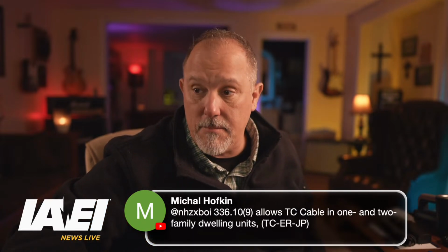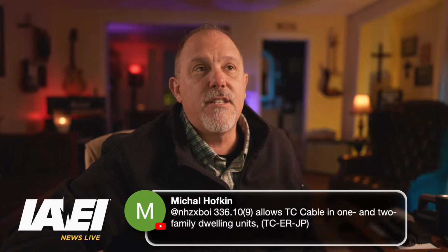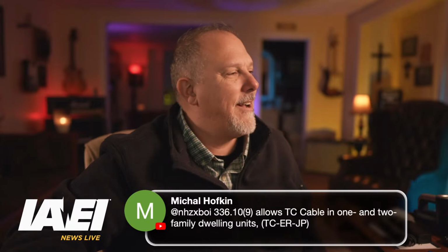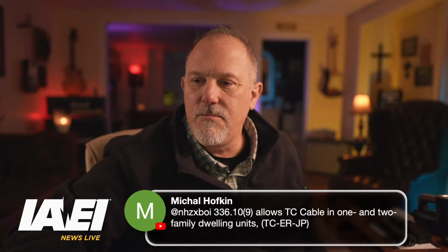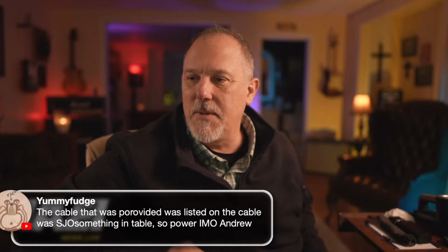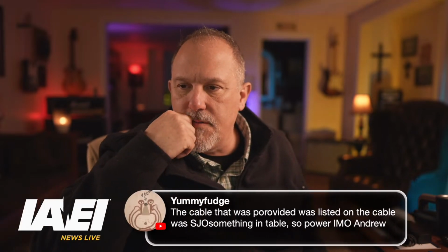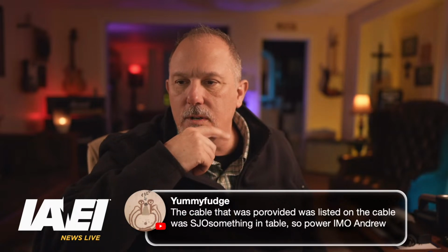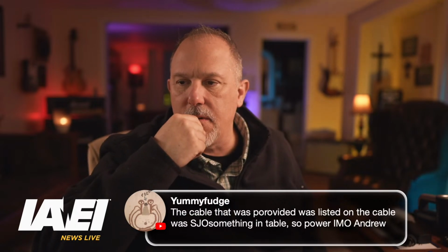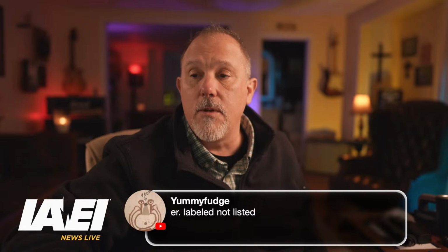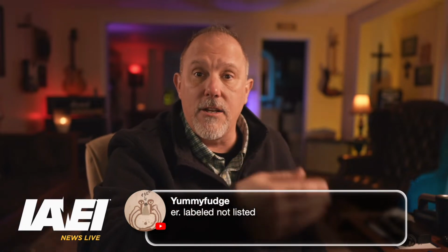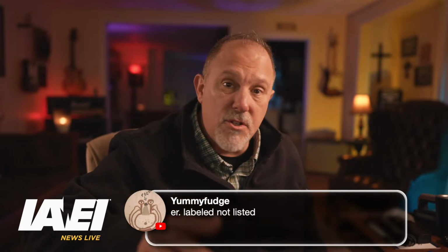I'm not sure what the JP means, but TCER, just put it in. I don't know, JP has to be at the end. The cable that was provided was labeled SJO something, in my opinion, Andrew—labeled and not listed. So you'd really have to look to determine whether it's communications or not. You'd have to look at what conductors are inside. I've seen some conductors where there's a power conductor and communications together. The insulation all has to be the same voltage rating, all that jazz, but that's covered by the standard.